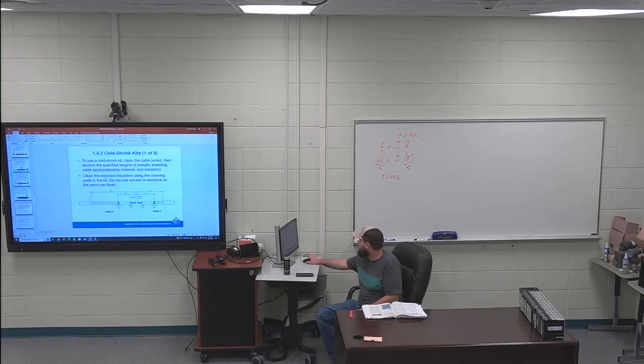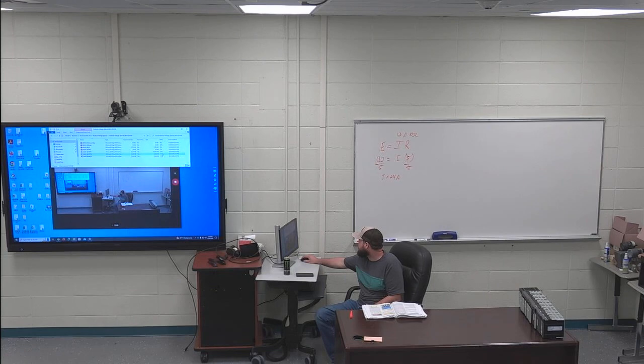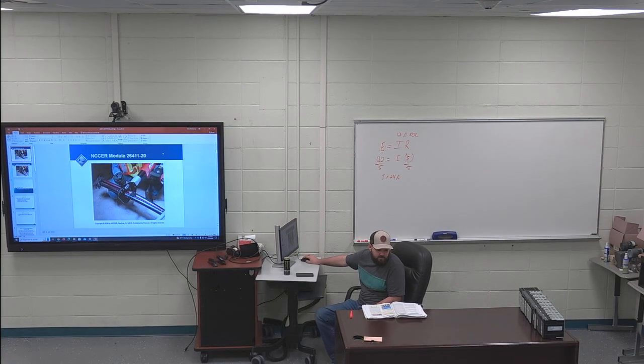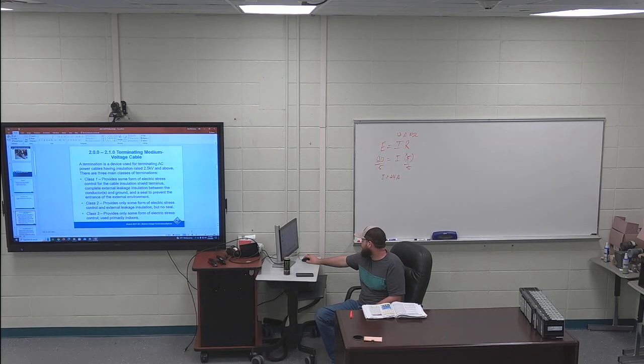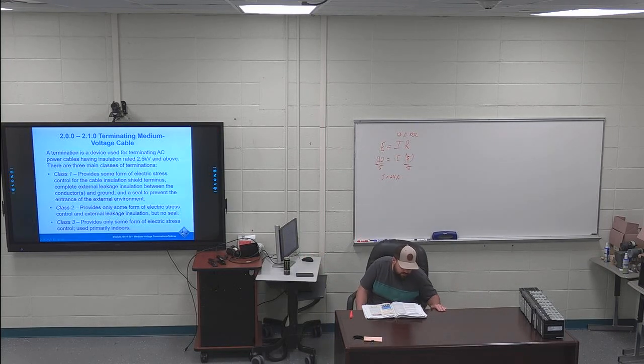Section 2 is going to be terminating medium voltage cable. You're going to have different classes for terminations. Page 24, termination classes. The whole, all the way from 210 all the way through that 3rd bullet point is highlighted. A class 1 cable termination, or more simply, a class 1 termination provides the following. Some form of electric stress control for the cable insulation shield terminus, complete external leakage insulation between the conductor and ground, and then key in on this last point.